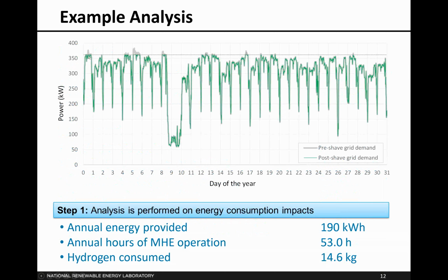When we run an analysis of peak shaving, it's actually a 15-minute analysis, we're estimating 190 kilowatt hours of energy provided throughout the year, and a total of 53 hours of operation. Throughout the year, we will be consuming just shy of 15 kilograms of hydrogen.